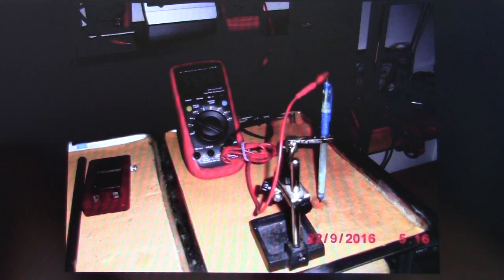Picture 49 is the same. It's a different reading, a different position of the probe in the electrolyte, 562.6 millivolts. Picture 50 gives a clear view of the measurement, 573.3 millivolts. Again, this illustrates that moving the probe on the soil changes the reading that we get.